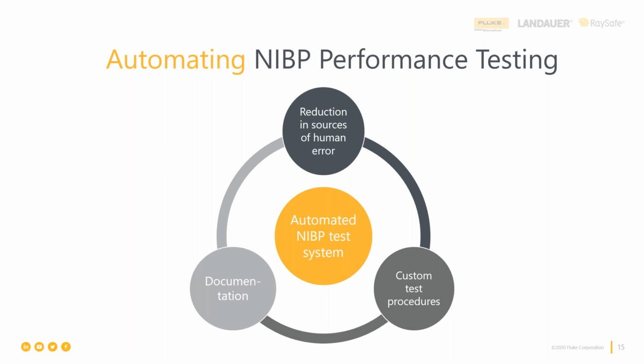in our workflow about NIBP testing. And so there's a couple of ways that you can look at this. Some test instruments these days that are designed for testing non-invasive blood pressure and invasive blood pressure provide a kind of onboard automation. Well, what's being automated here? What's automated is configuring the test instrument for the measurement that we want to make and automatically collecting the measurement value and perhaps even assessing it against the pass-fail criteria that are established in the manufacturer's service manual test procedure.